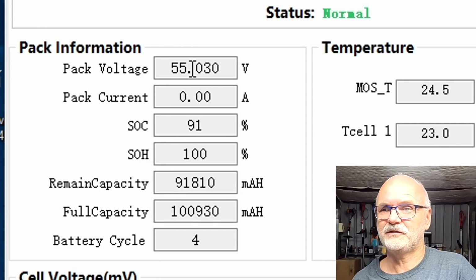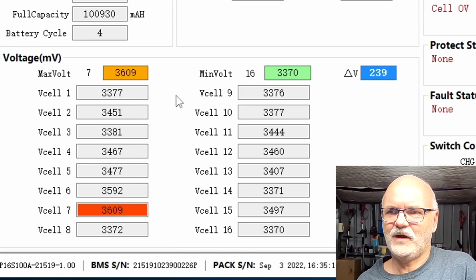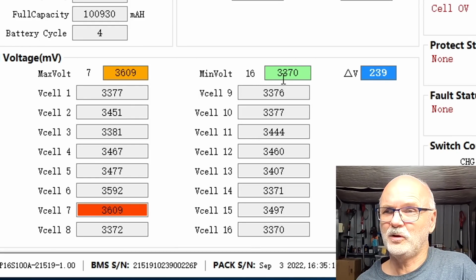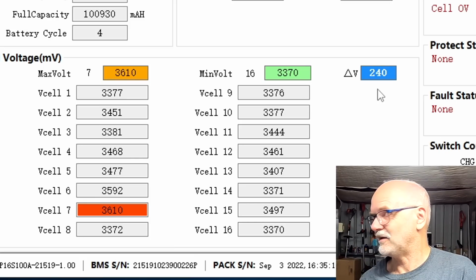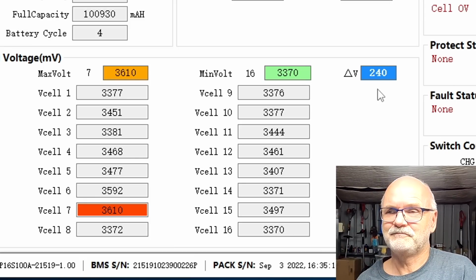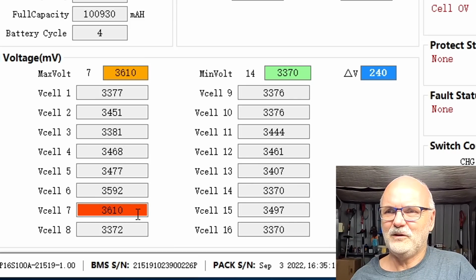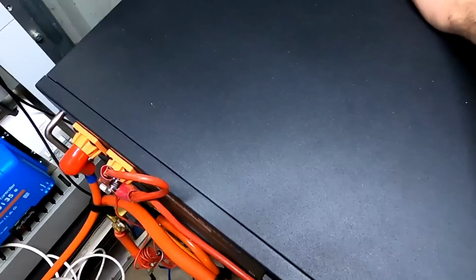We are at 55 volts. It seems to be a very, very unbalanced battery. The lowest cell is cell number 16 at 3.37. That's under 3.4. And the highest is over 3.6 already. See, it increased again by 2 millivolt. 190 milliamps going into the battery. And I don't think we can actually increase the voltage to 55.2, because then we will have an overvoltage protection situation for cell number 7. Very, very unbalanced. Alright, I'm not happy with that at all.